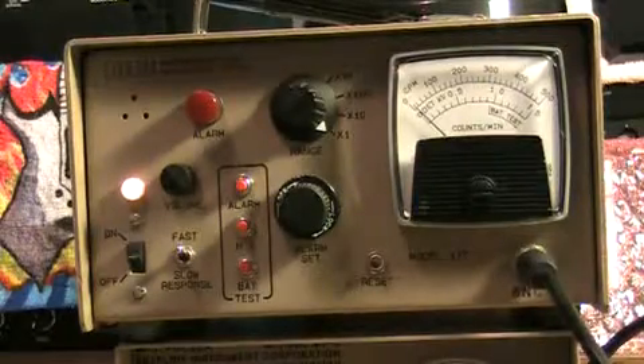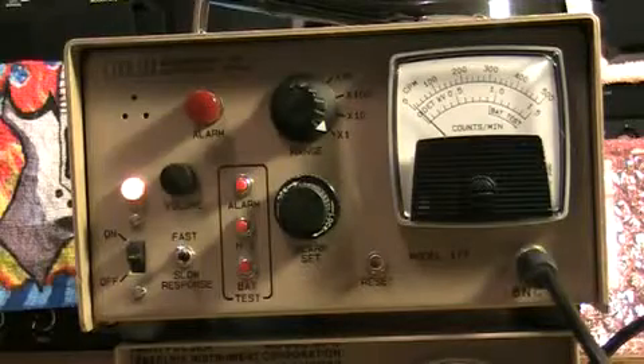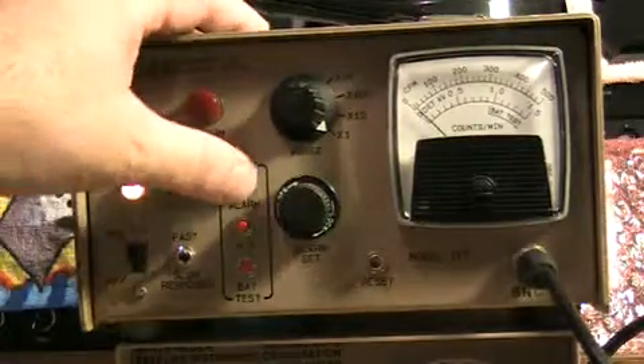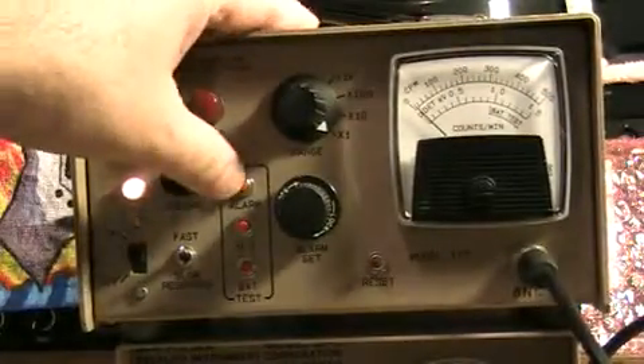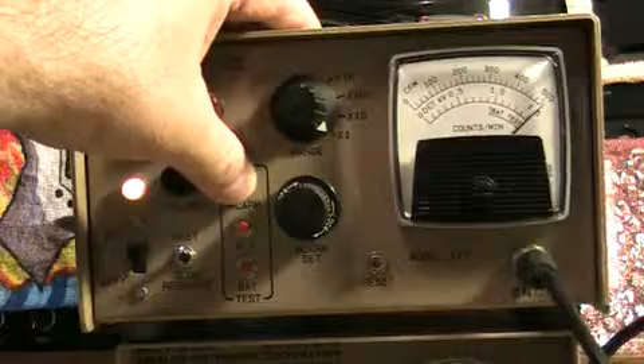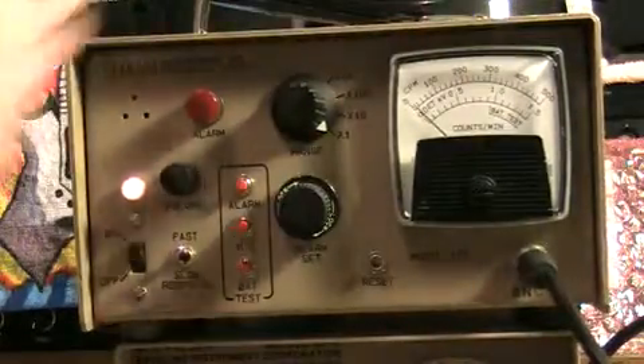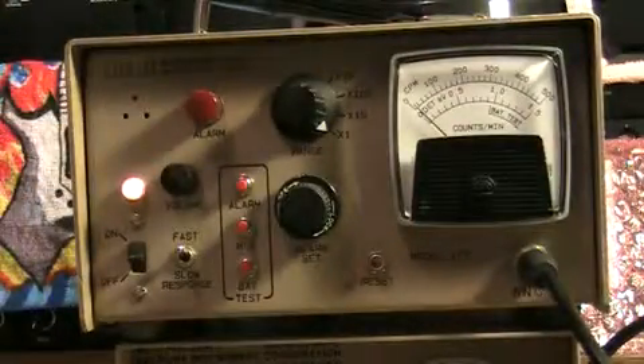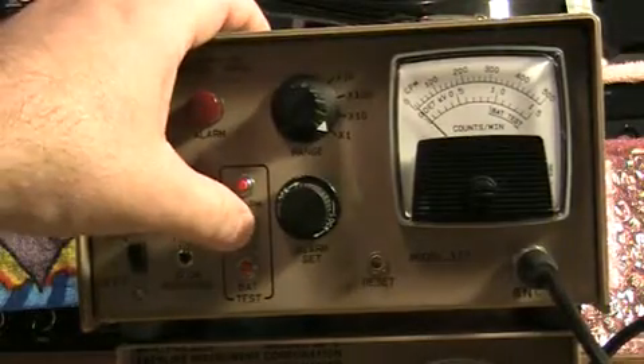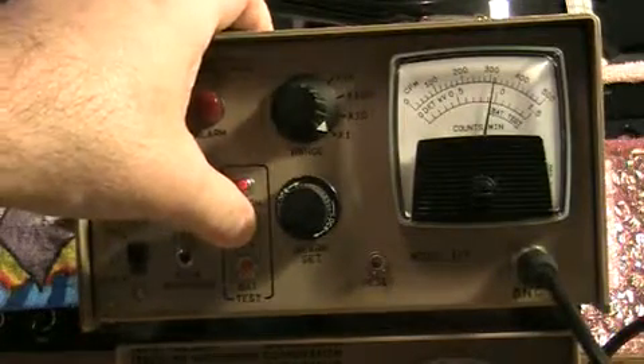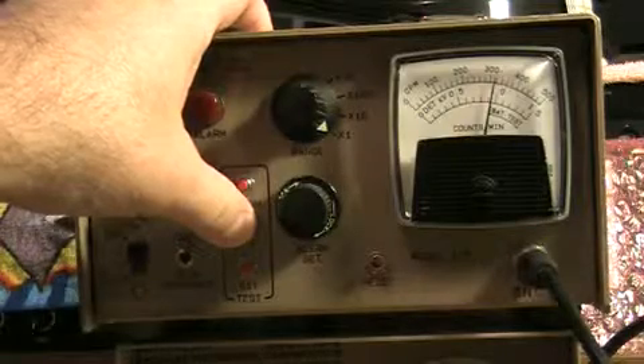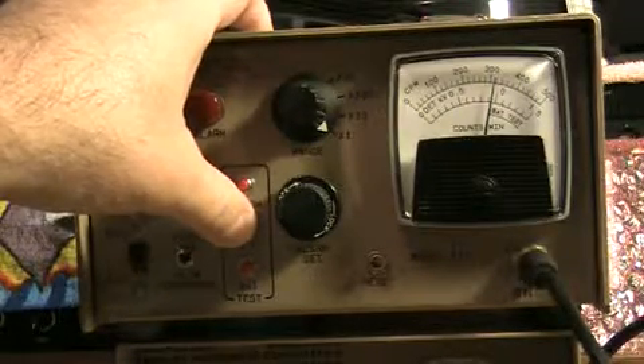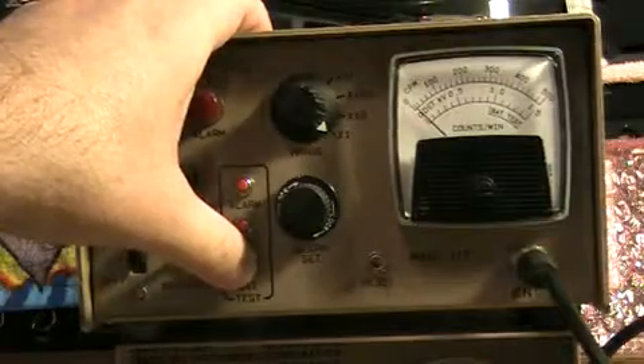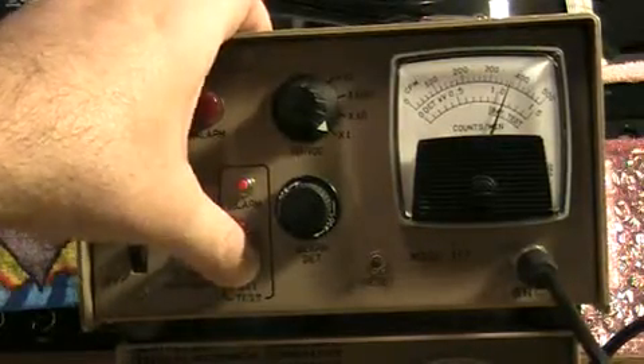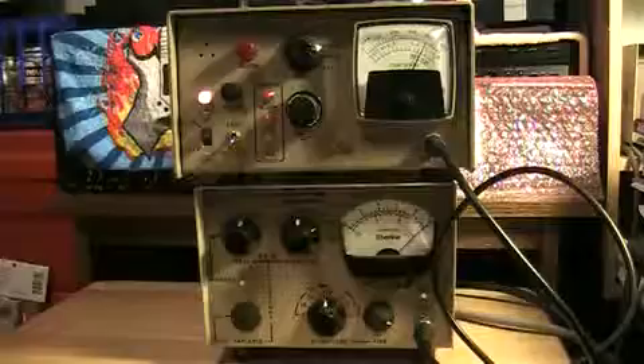And the Ludlum 177 does have some front panel adjustments. Here's the alarm. If the counts exceed a certain point on the meter, the alarm will sound. And I would set pretty high. I would set right at full scale. So if it pegs the meter, the alarm will sound. It's very annoying. Here's your high voltage. Set for right at 900 volts. Standard Geiger-Müller tube voltage. And there's a battery in here, so I can test the battery, and the battery is good.